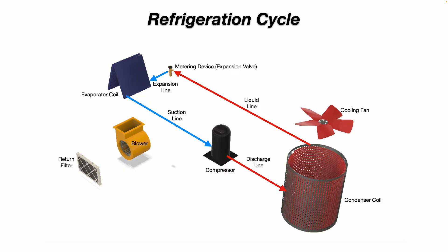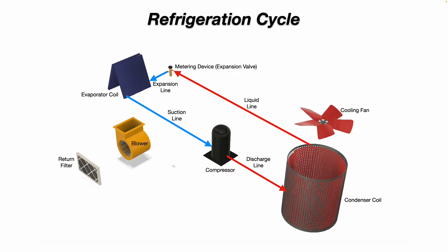As for how your indoor air actually gets cooled down: your ambient warm indoor air goes through the return filter into the blower. The blower blows that warm air through the evaporator coil, where the heat energy in the air molecules is given off to the refrigerant flowing through the evaporator coil. The refrigerant absorbs that heat energy — because by the law of thermodynamics, hot always goes to cold. That ambient air then becomes cool, leaves the evaporator coil, goes through your ductwork, and out your supply registers.